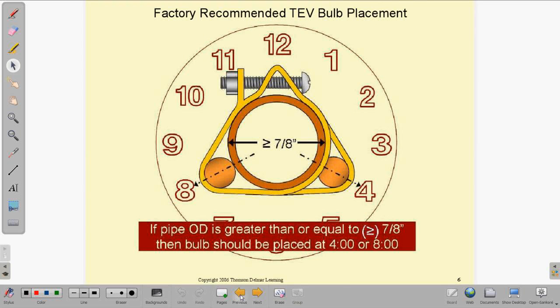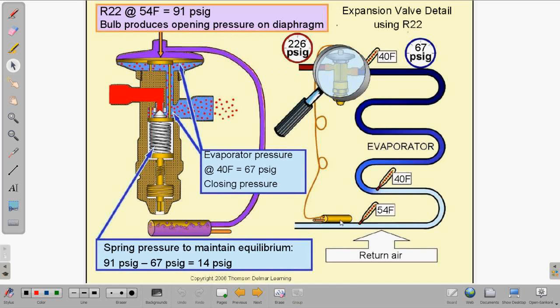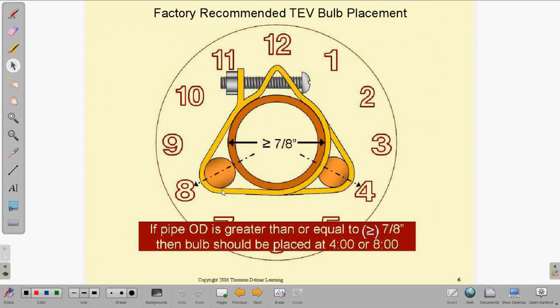Okay, so the sensing bulb that we're looking at here, where it's mounted on the outlet of the evaporator, it is important that you mount it properly. If the outlet of the evaporator's refrigeration piping is greater than or equal to 7/8 inch, you need to make sure that the sensing bulb is placed either at 4 o'clock as you look at it, or at 8 o'clock as you look at it. And we'll explain why in just a minute.